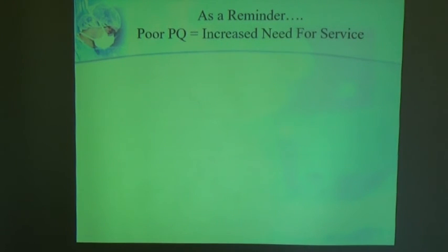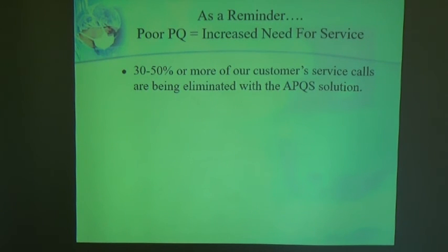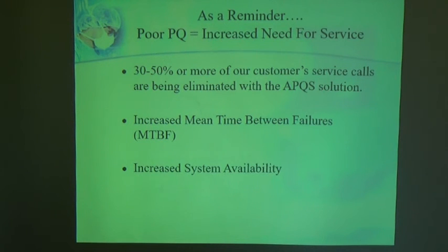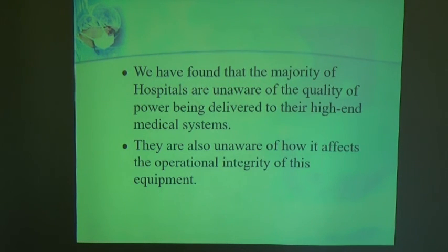As a reminder, poor power quality equals increased need for service. 30 to 50% or more of our customer service calls are being eliminated with APQS solution. They are realizing increased mean time between failures, increased system availability, and lower cost of service. We have found that the majority of hospitals are unaware of the quality of power being delivered to their high-end medical systems. They are also unaware of how it affects the operational integrity of this equipment.